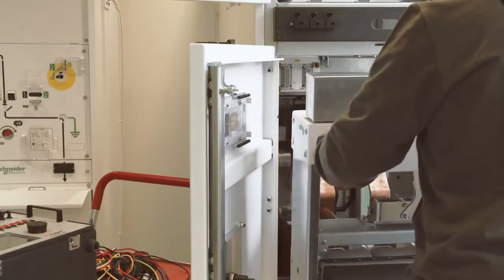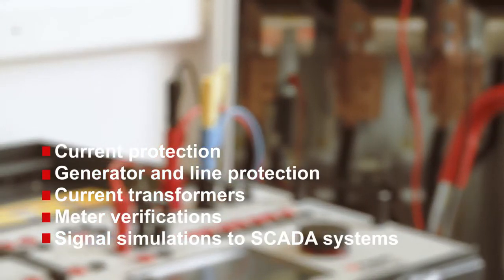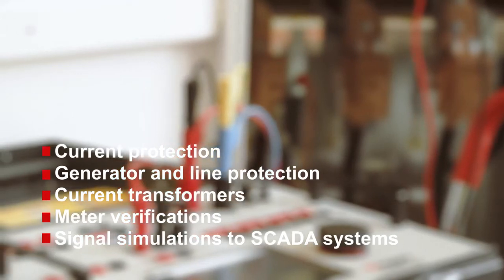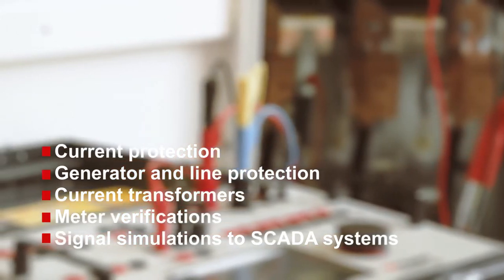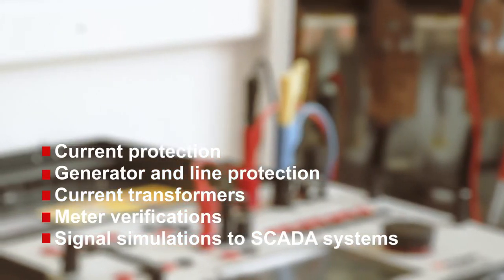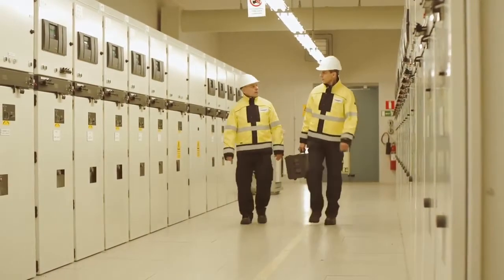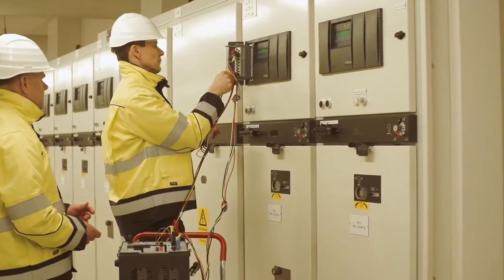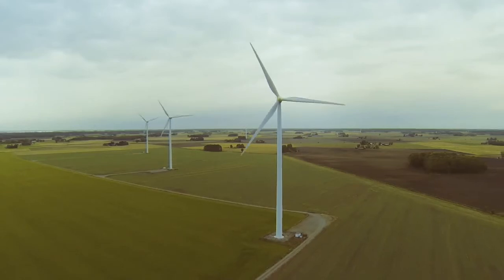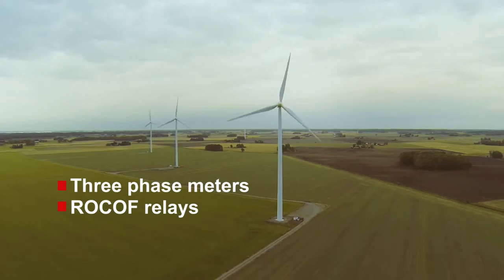The toolbox philosophy makes it possible to conduct a wide range of tests. The most obvious area is protection relays — for example, current protection in distribution grids, impedance space, generator and line protection, just to mention a few. Other common applications include basic commissioning and maintenance tests on current transformers. The capability of running three currents and four voltages simultaneously makes meter verification and signal simulation to SCADA systems quick and easy. The Sverker 900 is well suited to a wide range of environments, including smart grid and renewable energy applications where three-phase meters and ROCOF relays are commonly found.